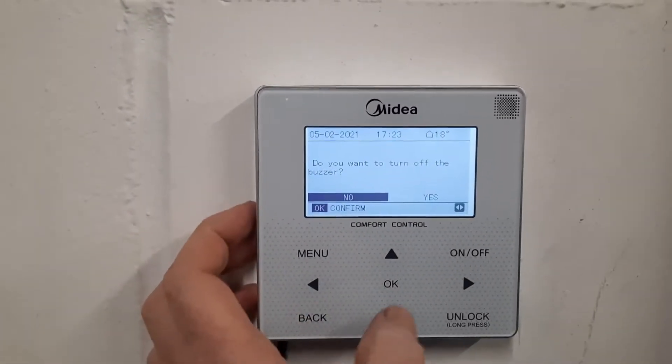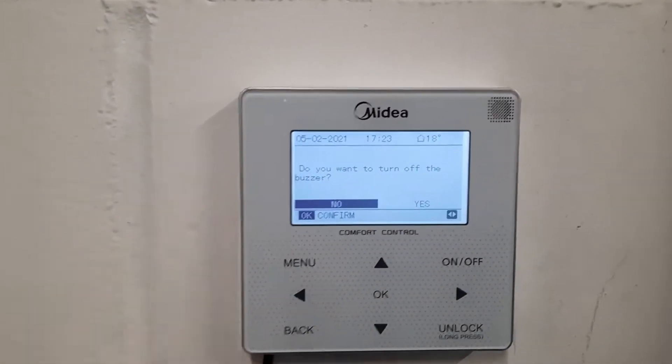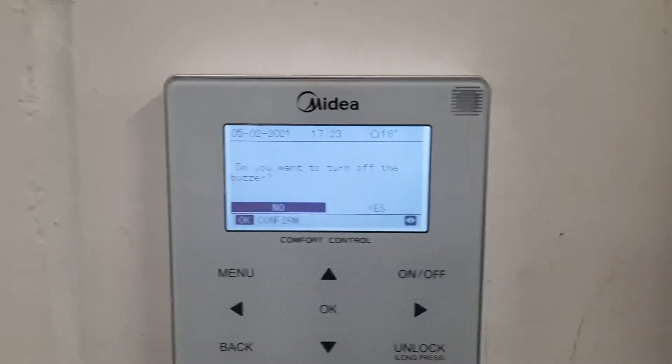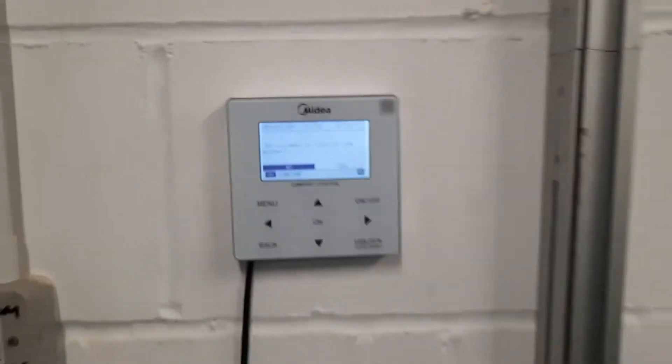If you look on the controller it says, or it would have said, it was a high-pressure alarm, but this machine doesn't have a high-pressure switch. It would have done historically.